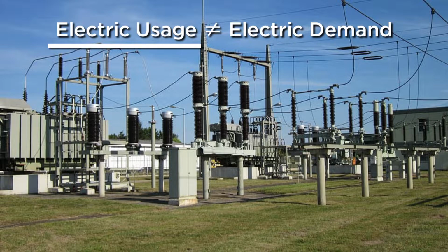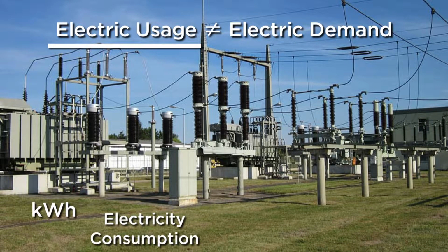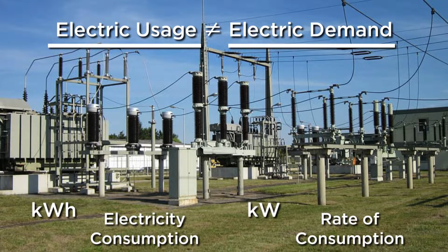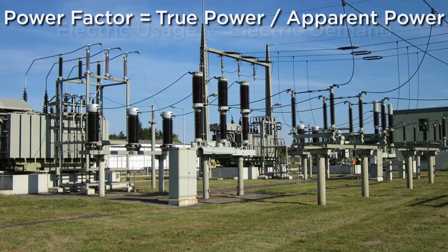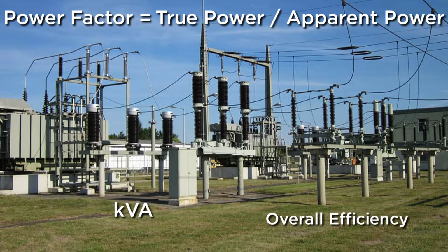Electric usage, which is commonly measured in kilowatt hours, or kWh, refers to the amount of electricity that is consumed during a time period. Electric demand, which is commonly measured in kW, or kilowatts, refers to the rate at which electricity is consumed. Utilities will often measure demand in 15 to 30-minute intervals and base your monthly charge on the highest recorded interval demand. Additionally, you should know that power factor, which is measured in kilovolt amps or kVA, represents the overall efficiency of your facility.